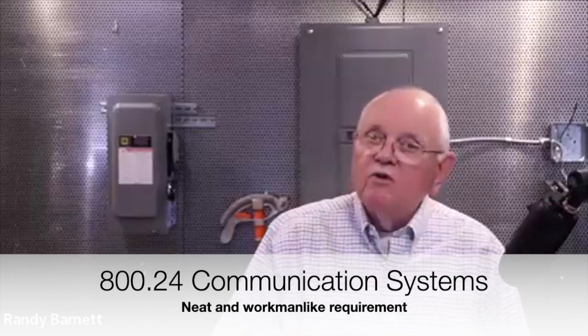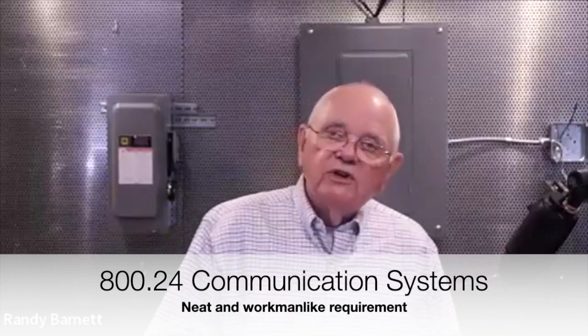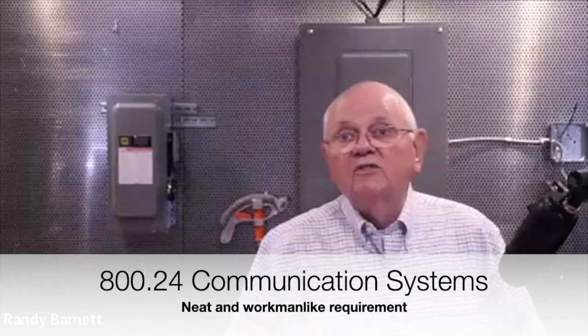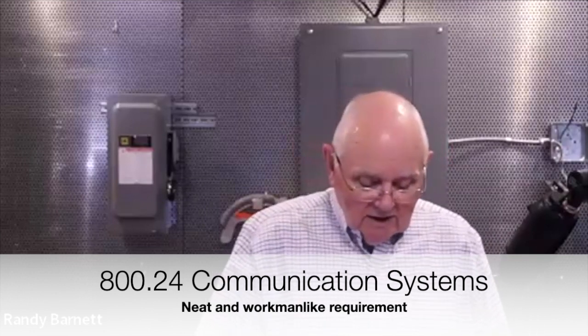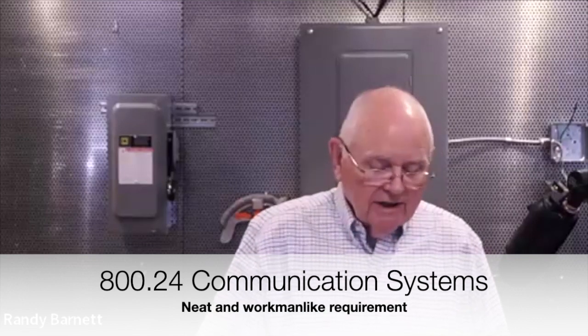So we do have references back in Chapter 7 to that term neat and workmanlike. In Chapter 8, now remember, Chapter 8 is our communication systems. It is a standalone chapter. The first 7 chapters don't apply. So if we want a requirement in Chapter 8 about neat and workmanlike, we're going to have to put it in there somewhere. So in Article 800, which is on the general requirements for communication systems, 800.24 again says circuits and equipment shall be installed in a neat and workmanlike manner.